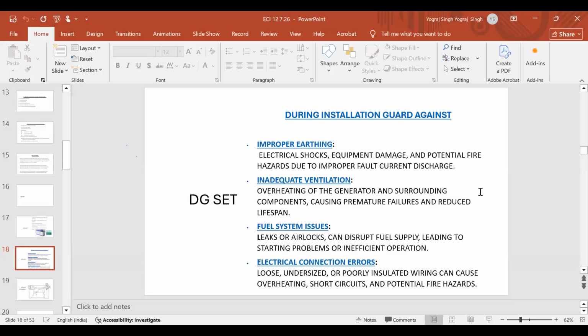Electrical connection errors, loose, undersized, or poorly insulated wiring can cause overheating, short circuit, and potential fire hazards. This is the ventilation I was talking about. Ventilation is important. Whatever heat is being dissipated by your DG set, it should quickly go away. Now, this DG set is inside an enclosure, and my exhaust system is taking care of heat dissipation. Next is internal electric supply, that is your wiring, etc.